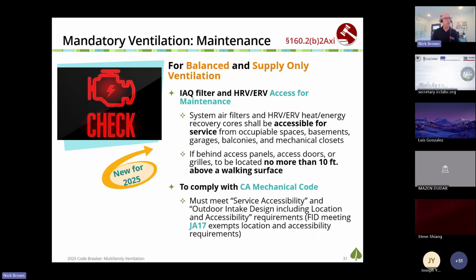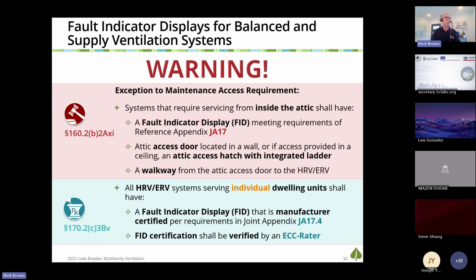And Joint Appendix 17 details these FID requirements. FIDs, fault indicator displays, are required if your filter is not accessible from within 10 feet. That way the FID alerts occupants or maintenance staff that there's a problem with the unit, that it needs to be looked at, because if it's not accessible, otherwise it's just going to keep running in failure mode.